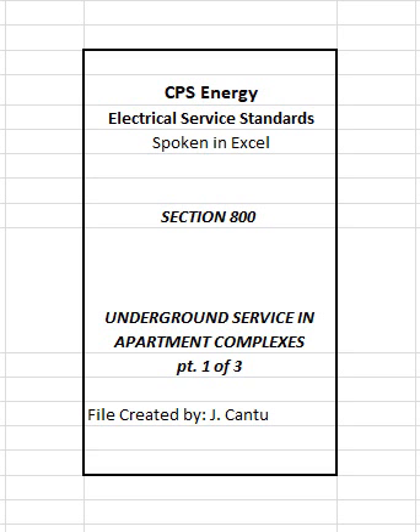1. All transformers, cable, or other CPS Energy facilities will be installed in accessible locations and the grade of the property at any transformer location must be 10% or less. All transformer pad sites are to be leveled by the developer. 2. No transformers, cable, or other CPS Energy facilities will be installed in areas that are prone to flooding. Any conduits installed across an earthen drain must be encased in 1500 psi concrete.